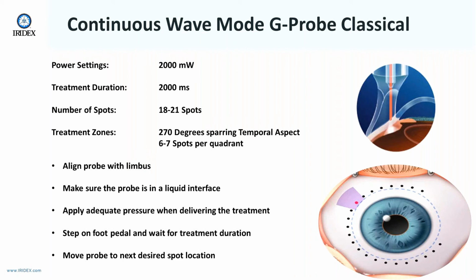Here are the settings for continuous wave mode in the classical sense. 2000 milliwatts power setting, a duration of 2000 milliseconds. Typically do 18 to 21 spots for 270 degrees, sparing the temporal aspects, 6 to 7 spots per quadrant. The technique is to align the probe with the limbus, make sure the probe has and is in a liquid interface, apply adequate pressure when delivering the treatment, step on the foot pedal and wait for the treatment duration. Then you move the probe to the next desired spot location.